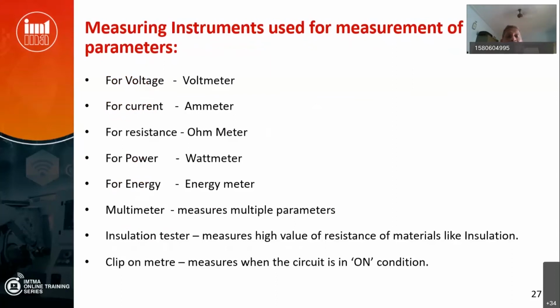And if you want to measure the very high resistance of an insulation, then an insulation tester. Many of us are more used to the name Megger. Megger is basically a company which manufactures insulation testers, but anyway in the field we call them Megger. So insulation testers measure very high resistance, and nowadays clip-on meters measure the current when the circuit is alive. And apart from that, we have plenty of meters.